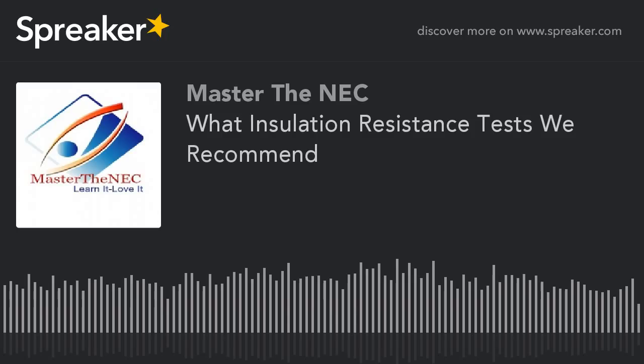But anyway, we're going to talk about the type of testing here on this show today. The two tests that we recommend are a spot test and a polarization index test. These are the two tests that we recommend if you're going to do the proper testing, whether you're going to do on-site dunk tank testing on your conductors on the reel, or use your insulated wire, electrical wire, or test cables or what have you. You just have to understand that you need to do it perfectly, and you need to understand its limitations.